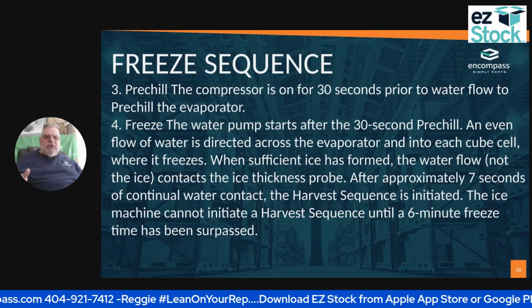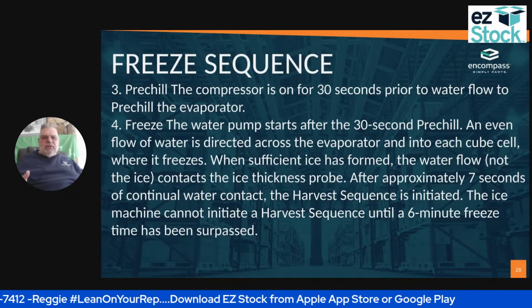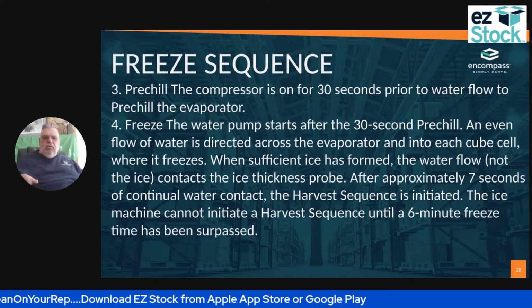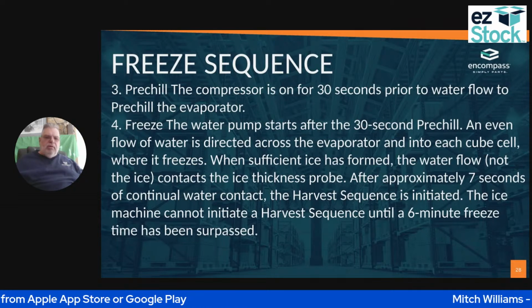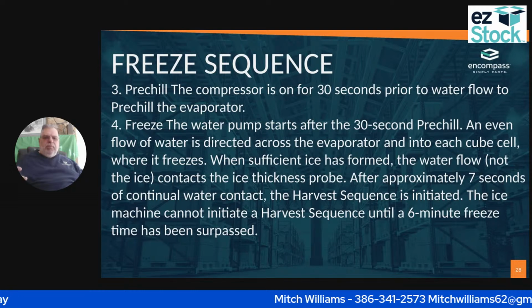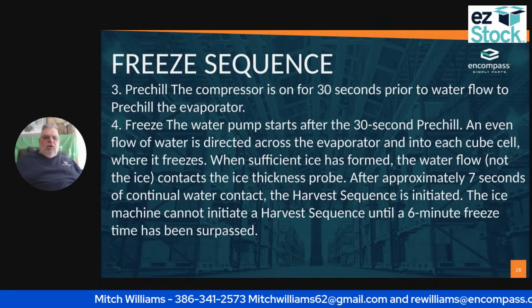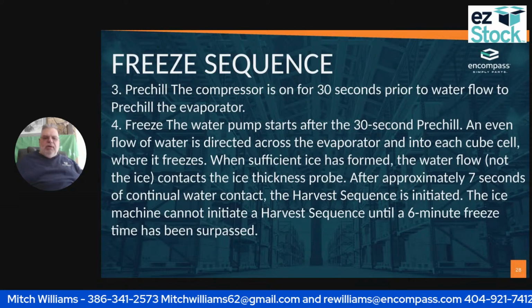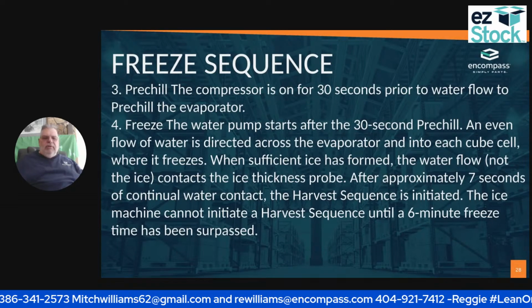It will pre-chill the compressor for 30 seconds to allow the water flow to pre-chill the evaporator. Then the water pump starts after 30 seconds of the pre-chill. An even flow of water is directed across the evaporator into each cell cube, where it freezes.